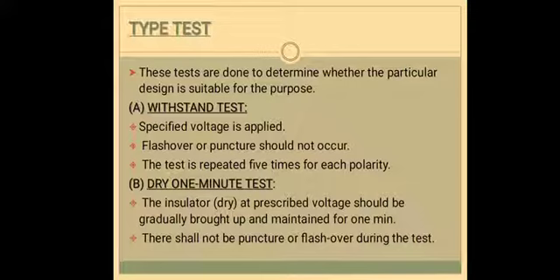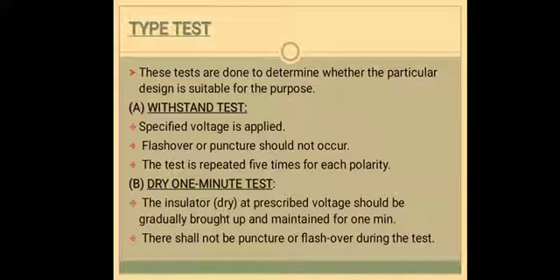Next is the dry one minute test. In this, the insulator will be cleaned and dried, mounted as specified, and the prescribed voltage should be gradually brought up and maintained for 1 minute. There should be no puncture or flashover during the test.